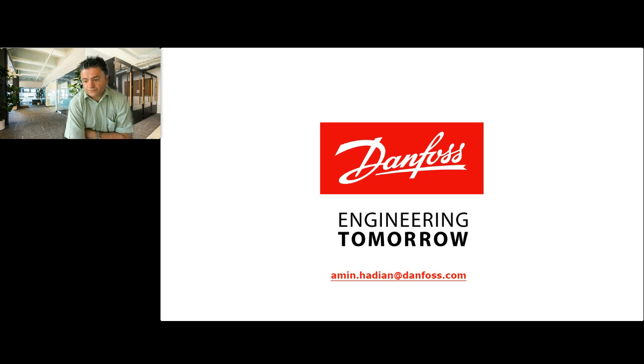Yeah. All right. Then we have one more question here. I mentioned that the standard is 8,000 hours, but we have some cases, for instance, where we overspeed the pump, and in that case we're talking about 500 hours. And then the comment is that it seems like a big jump. For sure, when you overspeed the pump from the maximum 1800 RPM, where we say 8,000 hours in between service, and then speed it up to 2400 RPM, which is the maximum, in that area we are saying 500 hours.